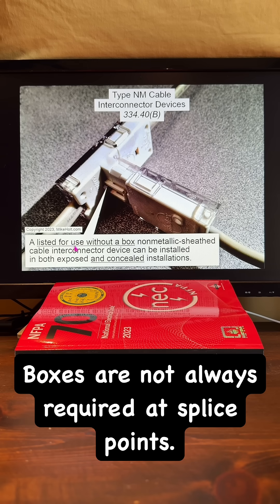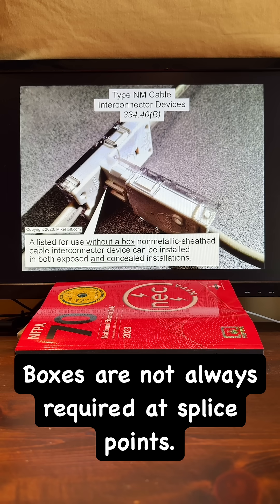It says a listed for use without a box non-metallic sheath cable interconnector device can be installed in both exposed and concealed installations, either during new construction or after new construction — it doesn't really matter at all. I'm sure that statement would drive dinosaurs nuts.